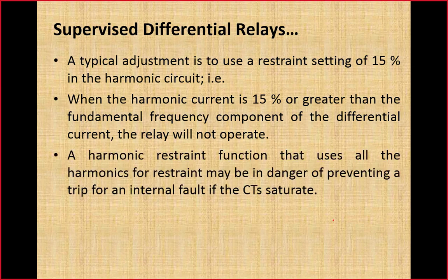So a harmonic restraint function that uses all harmonics for restraint may be in danger of preventing a trip for an internal fault if the CT gets saturated. So this is a problem. If we are utilizing all the harmonics to restrain the operation of the relay, it is quite possible that for an internal fault, if the CT gets saturated and the differential current is full of harmonics, the relay is not going to operate. If the relay is not going to operate, it means protection has failed.